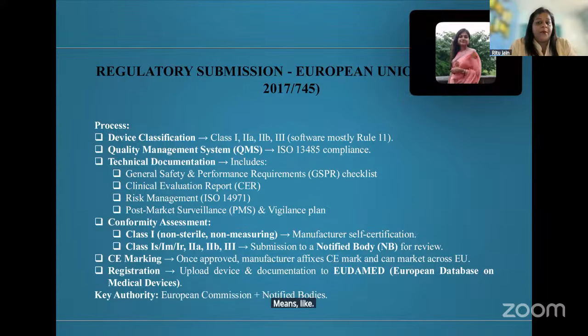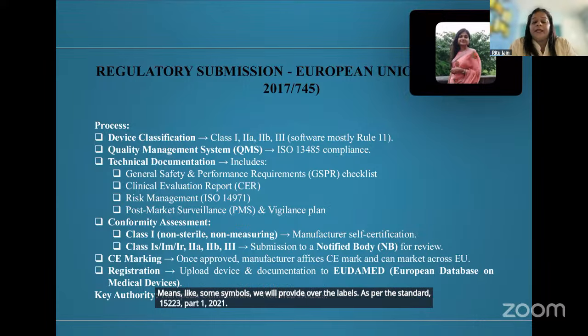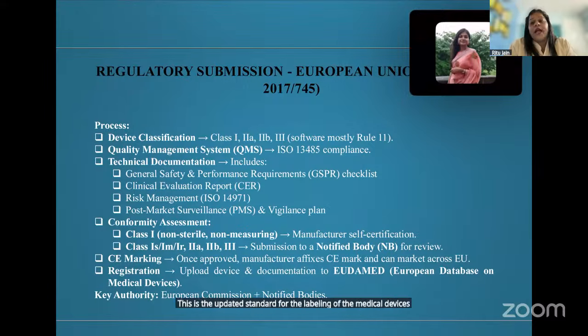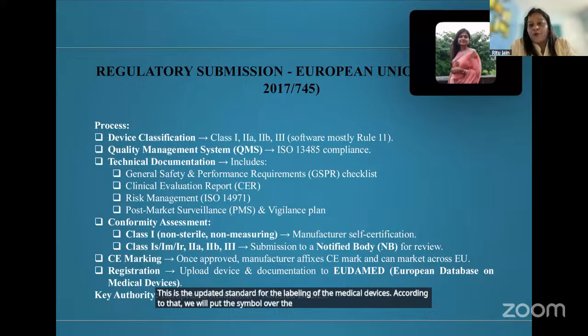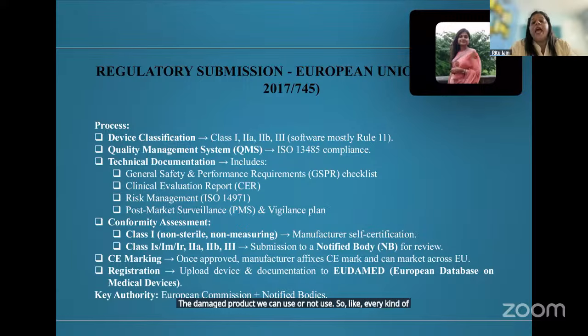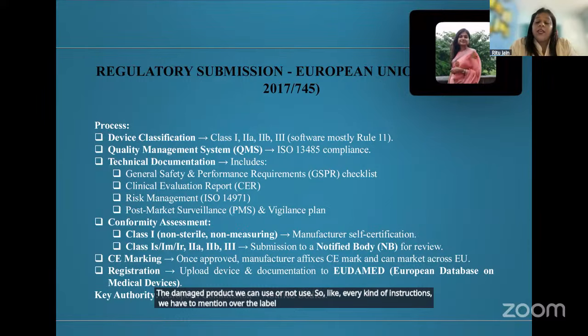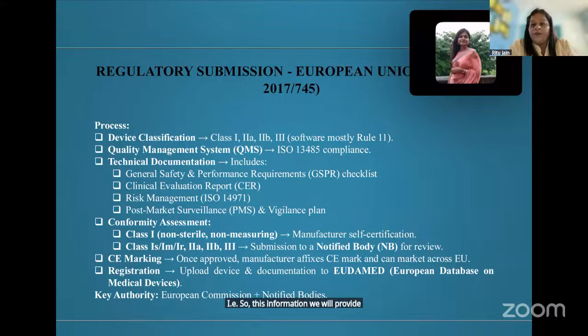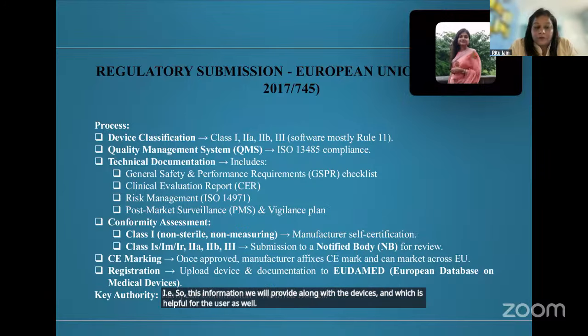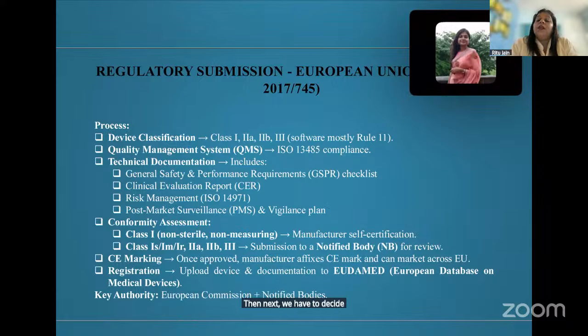We will provide some symbols over the labels as per the standard 15223 part 1 2021. This is the updated standard for the labeling of medical devices. According to that, we will put the symbols over the labels and the IFU. It means whether the product is sterile or non-sterile, whether we can reuse it or not, whether a damaged product can be used or not. So every kind of instruction we have to mention over the label and the IFU. In the IFU you have to mention the warnings, precautions, product detail, sterilization method, mode of action, and the relevant symbols. This information we will provide along with our devices, and it is helpful for the user as well.